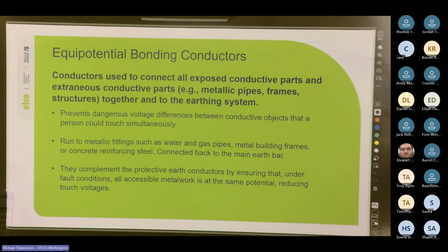Cool. So equipotential bonding conductors, it's about keeping everything at the same level. If two pipes are at different voltages during a fault, touching them could complete the circuit through you. So bonding straps need to tie the two pieces together so there's no potential difference. So when plumbers cut copper pipes under the house, we didn't used to use earth stakes. We used to use the copper pipes as our earth. So you'll find that in old homes. And what plumbers would do is they didn't realize there was current flowing through the earth. So they would cut the copper pipe, but then they would touch both sides of the copper pipe at once, becoming a conductor. So what they're supposed to do is take a 4 or 6 mil earth, strap it to either side of the bit of pipe that they're cutting, and then cut. So that way there is a continuous earth path that is not us.